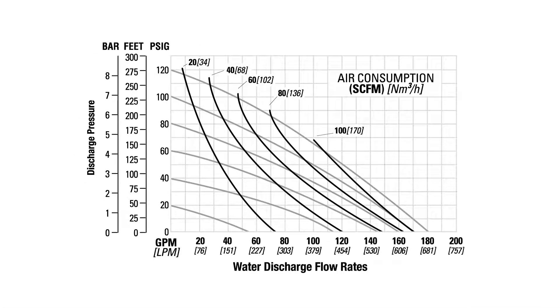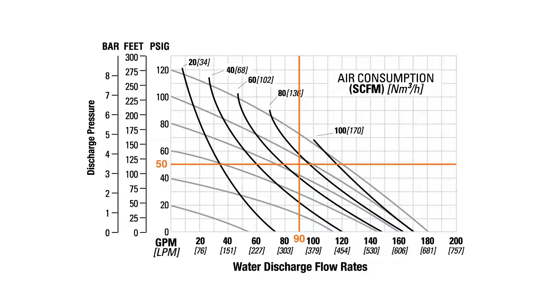The AODD pump performance curve defines the pump's performance based on a specific operating point, utilizing the required gallons per minute at a certain discharge pressure. For example, a manufacturing plant requires an AODD pump to pump 90 gallons per minute at a discharge pressure of 50 PSIG. To find out how well the pump will perform, find 90 gallons per minute along the horizontal axis, then follow the line up to 50 PSIG on the vertical axis. The area where these two axes intersect is the operating point.